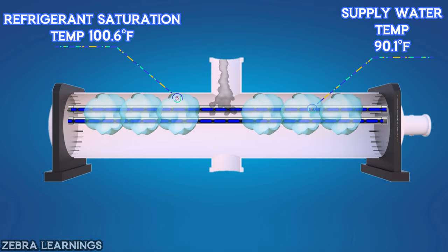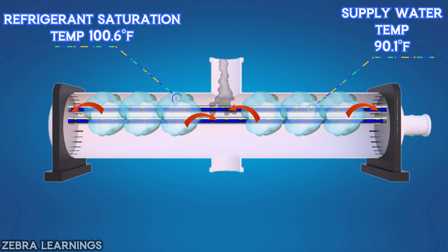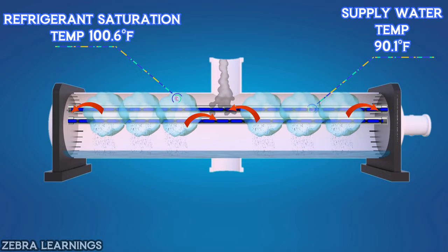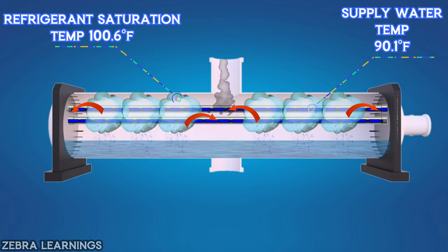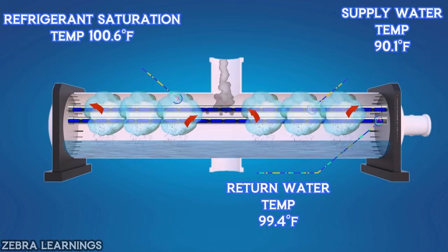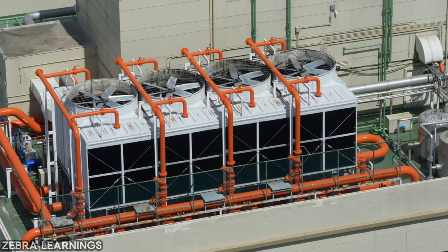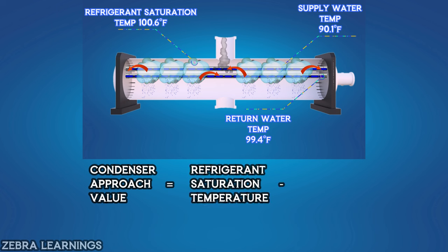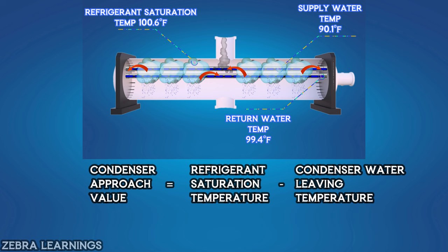Heat is transferred from the high-temperature refrigerant to the low-temperature water, causing the refrigerant to decrease in temperature and change from vapor to liquid. Since the heat from the refrigerant is transferred to the water, the water leaves the condenser at 99.4 degrees Fahrenheit, then goes to the cooling tower where it is cooled before returning. The condenser approach value equals refrigerant saturation temperature minus condenser water leaving temperature: 100.6 degrees Fahrenheit minus 99.4 degrees Fahrenheit equals 1.2 degrees Fahrenheit.